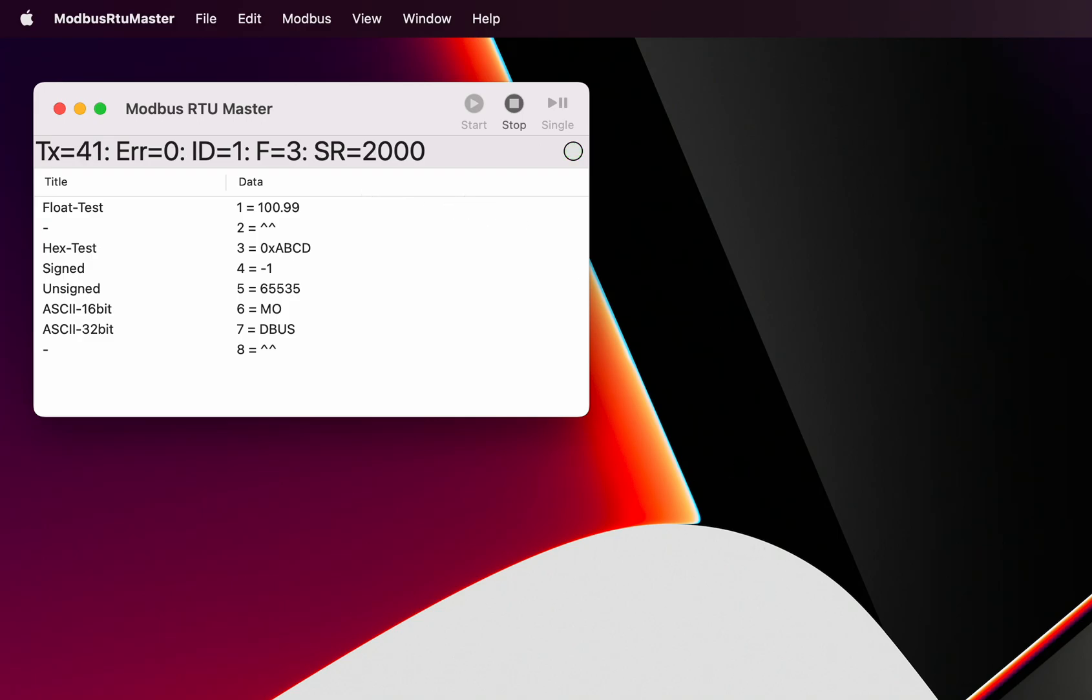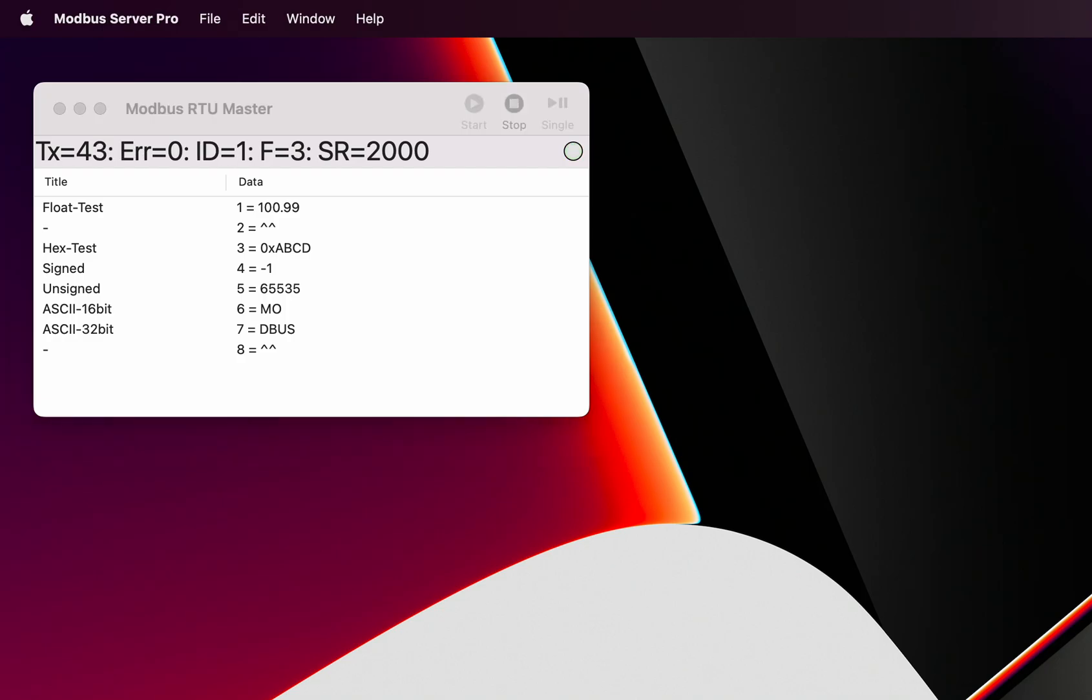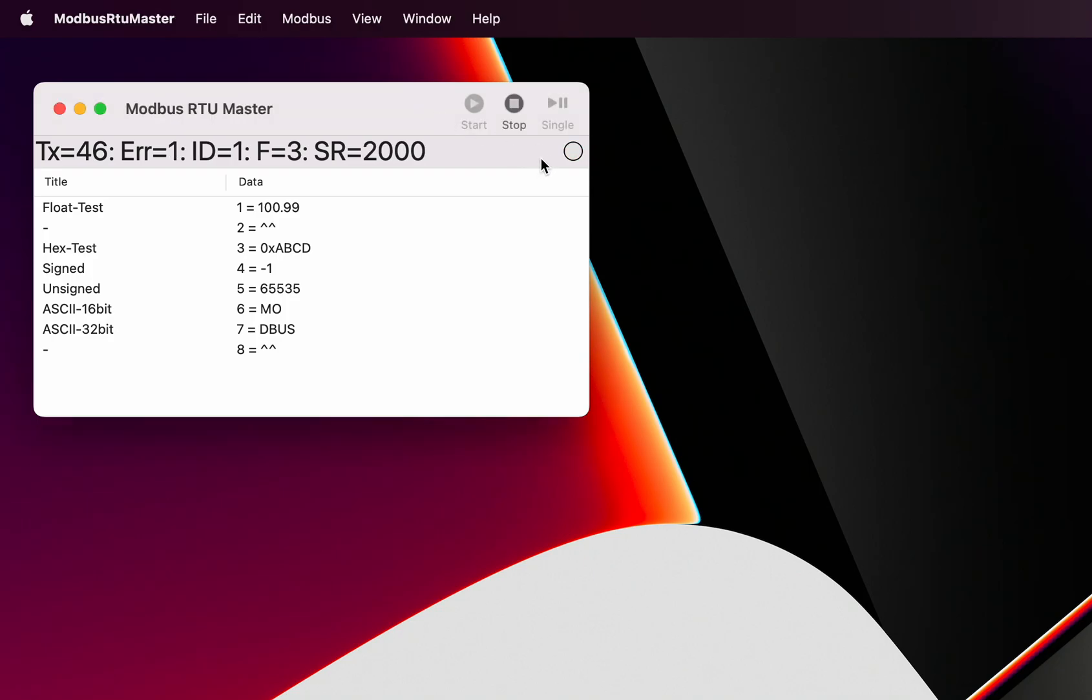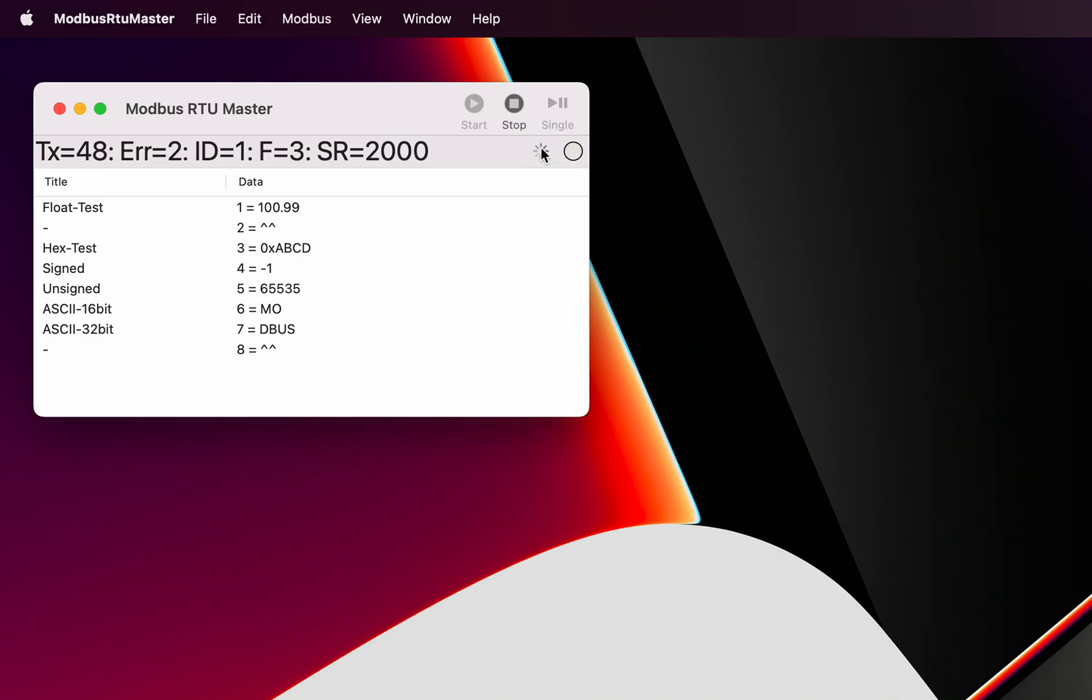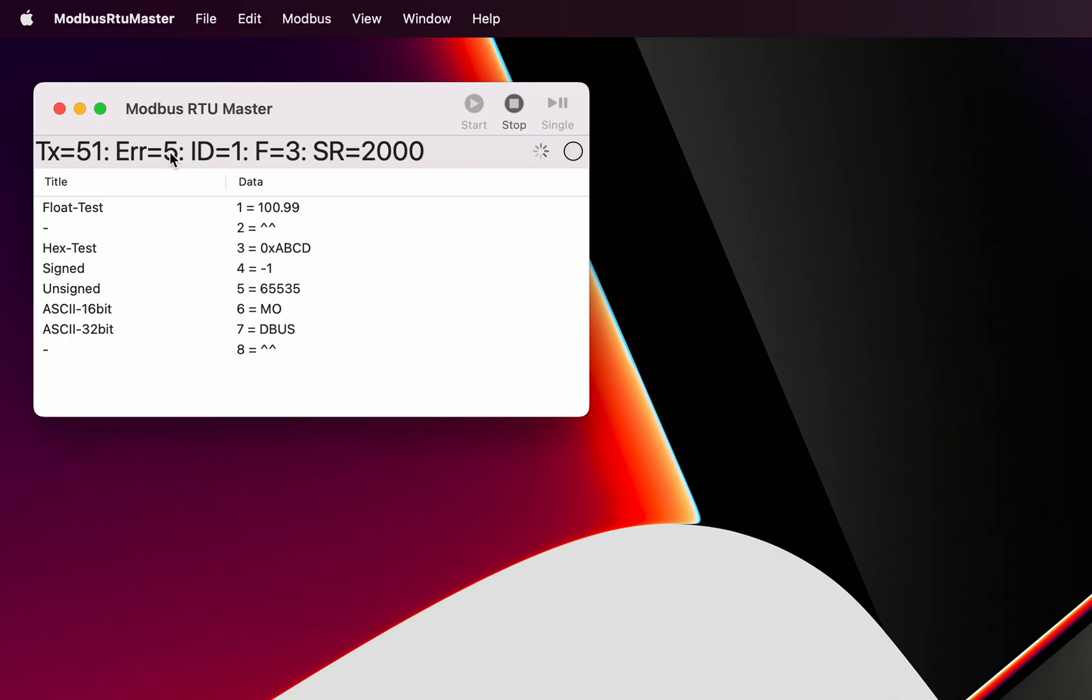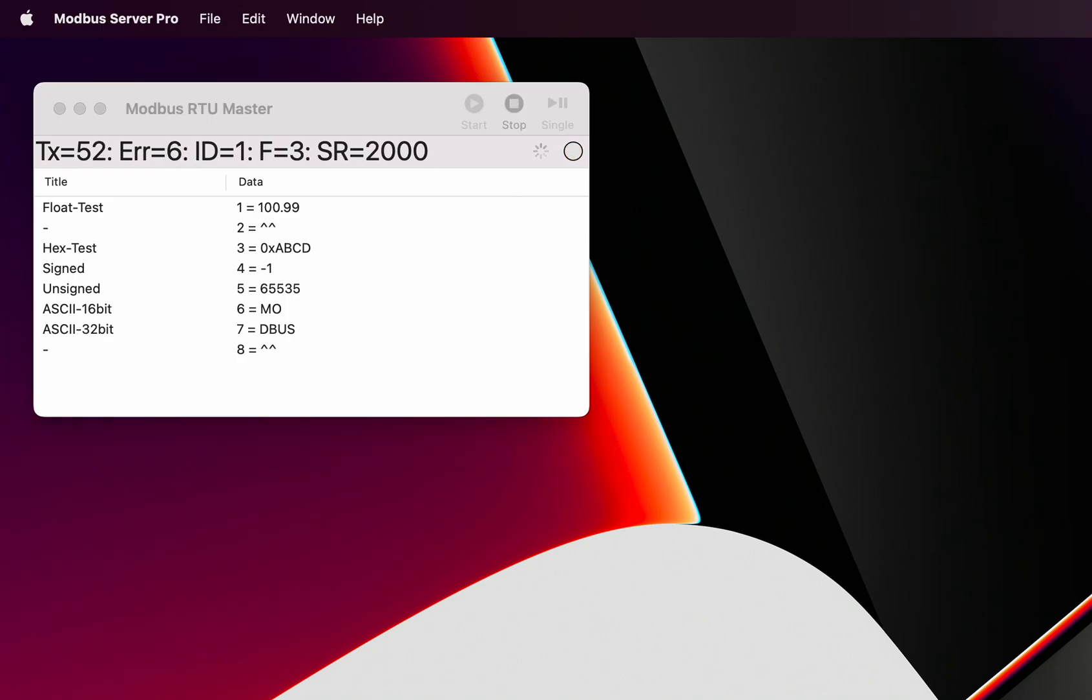Just for a little demonstration, I'm going to make the slave not respond. So now the slave is not responding, you can see the progress indicator stays on and it eventually comes back red. The error count of course is going up. So now we can see every time we do a transmit, for each transmit the error count goes up as well. That's what happens when there's no response or when there's some sort of error response or faulty response from the slave.